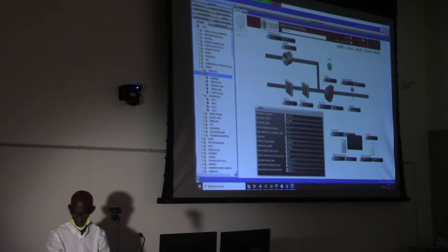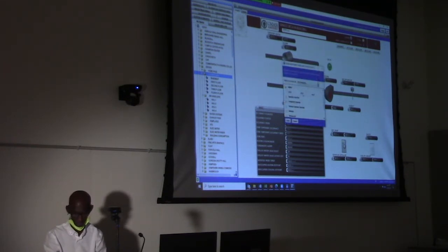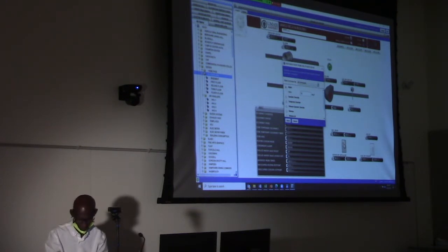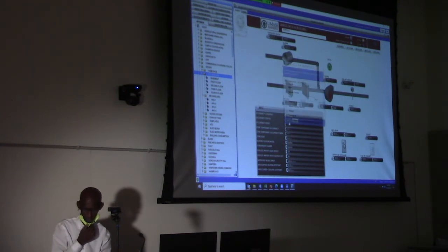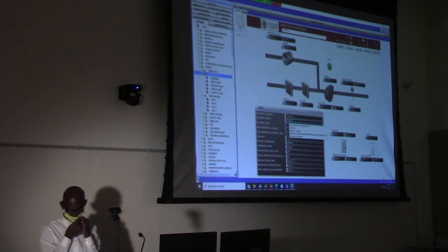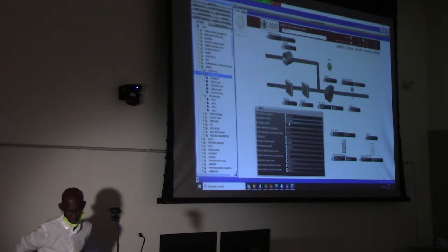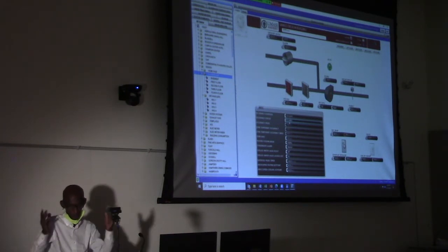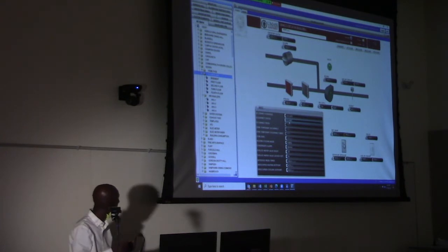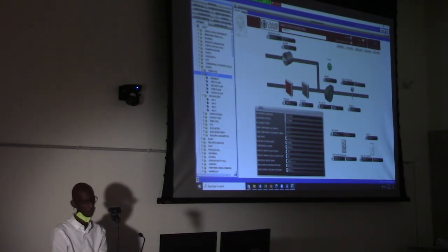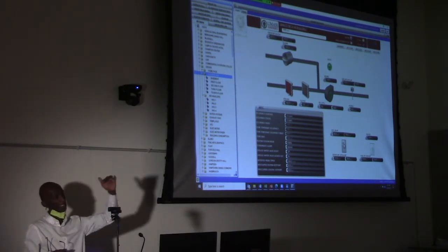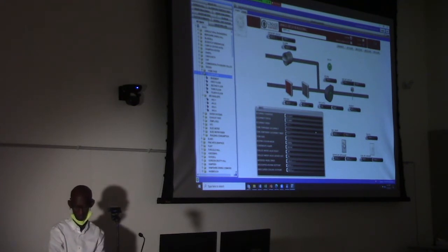I can't guarantee it's going to work, but let me see if we can override these to 72 degrees and see if it keeps it. Override these, 74 degrees. See, this is what they don't let me do. Okay, it's starting. That's good news. There you go. And you can see the heating coil. It's red and it's 100%. So it's taking the air and heating it to get to 74 degrees.